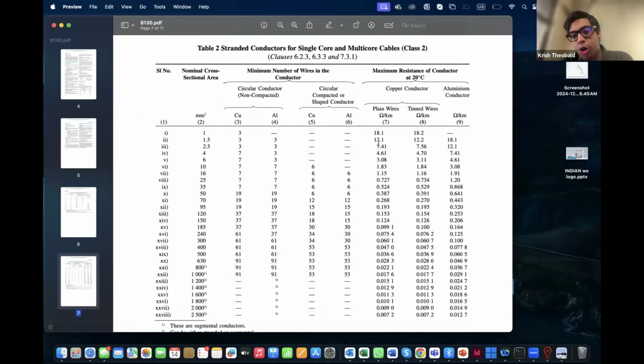In some European standards, they talk about 0.08 milliohms per meter. In smaller circuits, where 18.1 is the resistance and 0.08 milliohms per meter is the reactance, that's very negligible. But beyond 240 square mm, the resistance is lesser than the reactance. European practice is that for anything above 25 square mm, 0.727 is the resistance and 0.08 is the reactance. So that's a 10% difference, and above 25 square mm you consider the reactance as well.